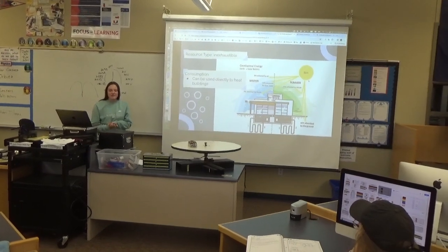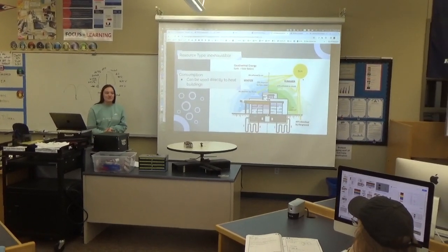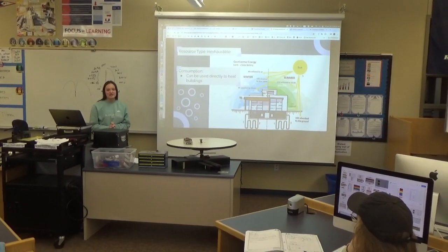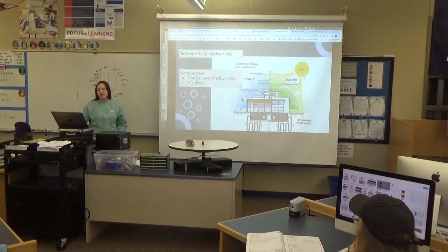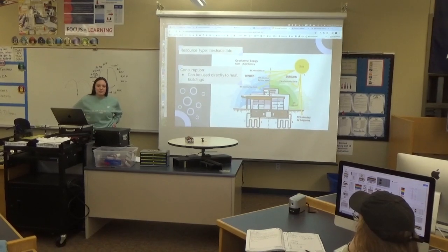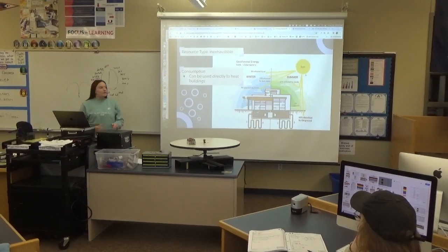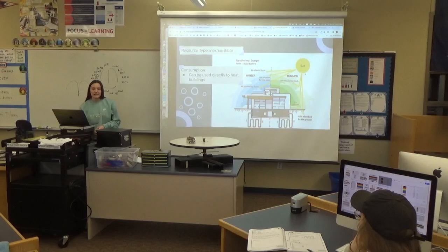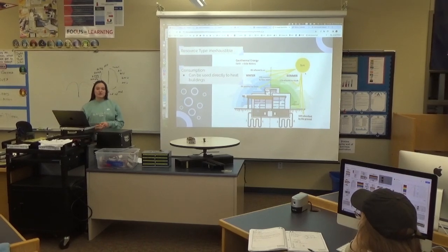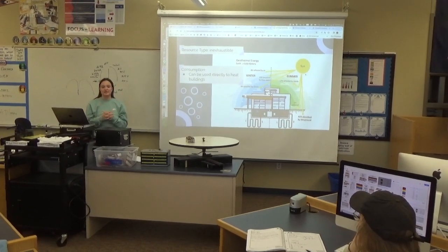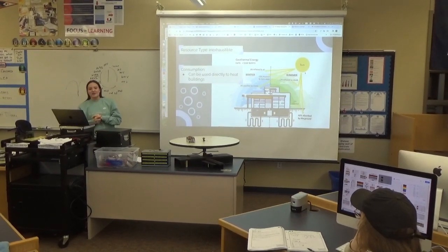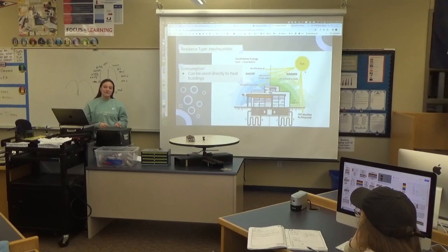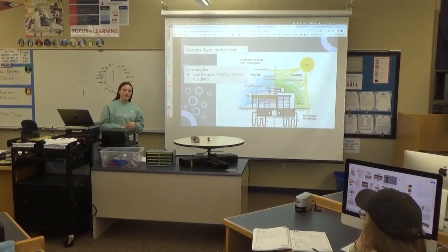When you're talking about using geothermal as a consumer, there are two main ways that you can do it. You can use it to directly heat a building, or you can use it to produce energy, like from a geothermal power plant. When you're using it to directly heat a building, you use a ground heat exchanger. A series of pipes called a loop is buried in shallow ground, which is the upper 10 feet of the earth. And this shallow ground keeps a constant temperature of around 50 to 60 degrees Fahrenheit throughout the year.